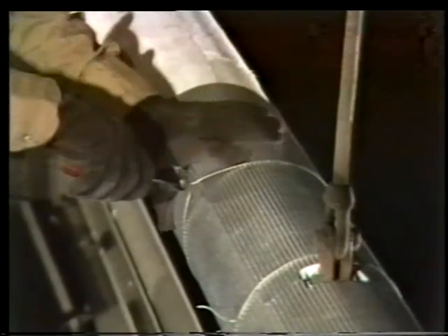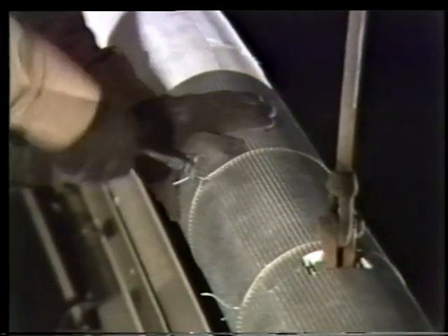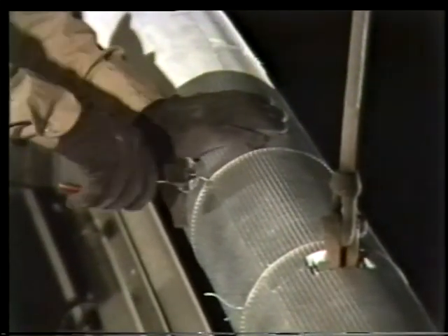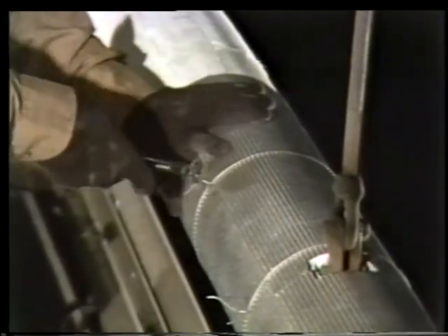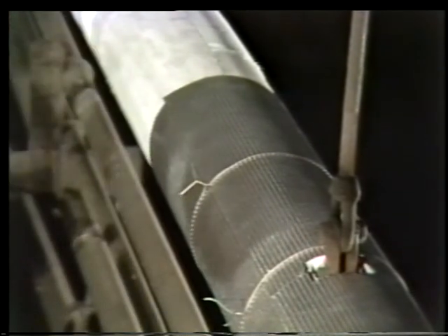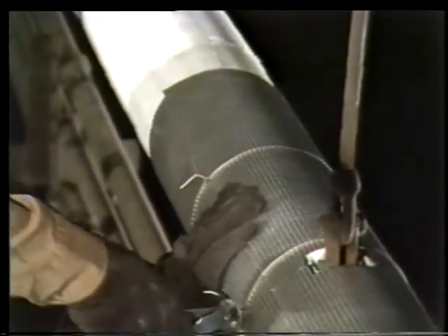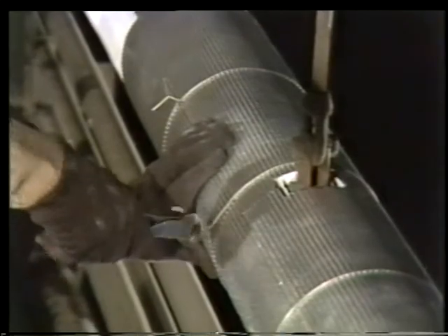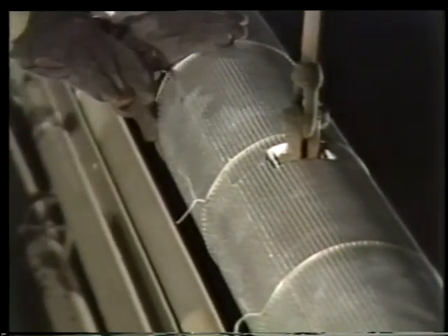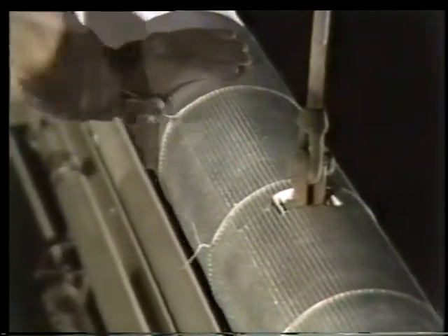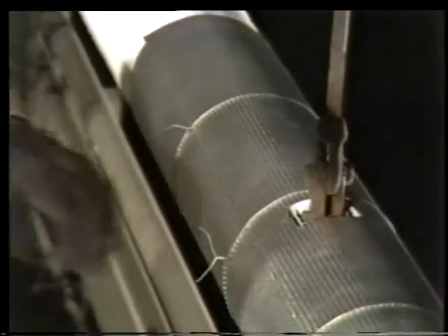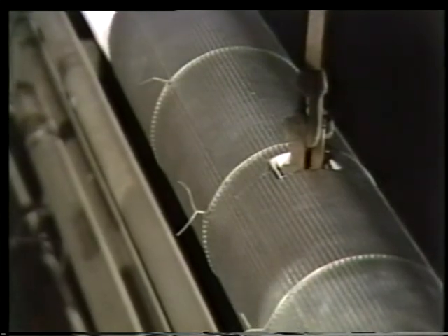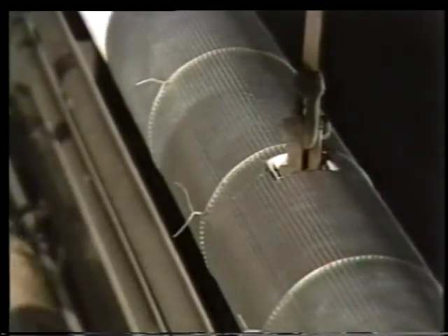When all the wires for a single jacket are in place, they're twisted tightly so the jacket fits snugly, but not so tight that the wire breaks. Remember, the metal jackets don't give like the insulation itself. The wires aren't embedded in the surface. The object is to hold the jacket in place so it forms a smooth, tight shell over the insulation with no buckling or loose spots. When the jacket is firmly in place, it can be banded.